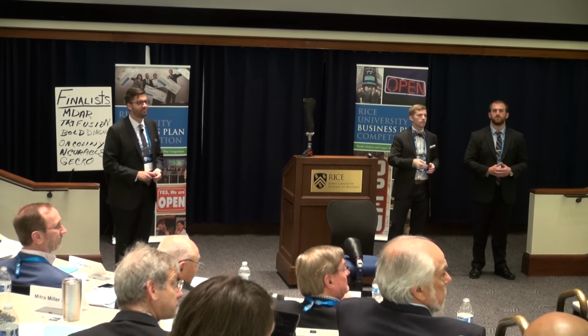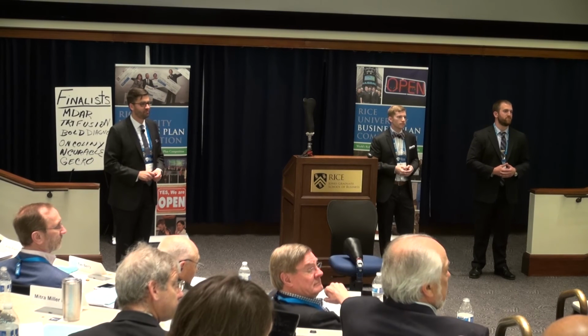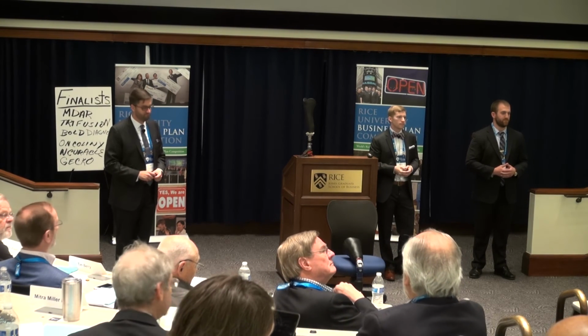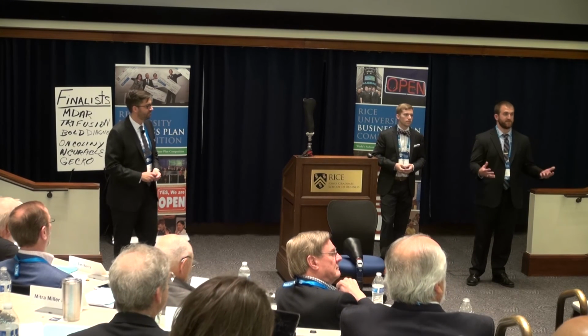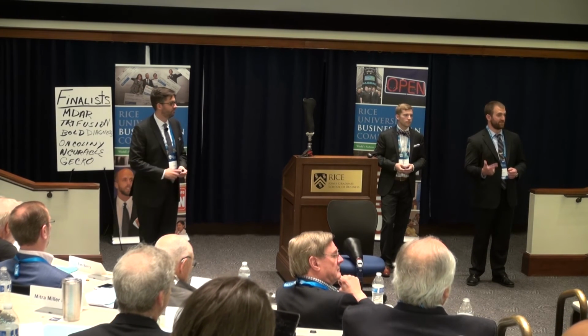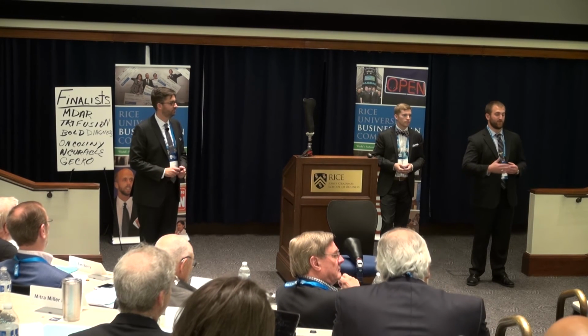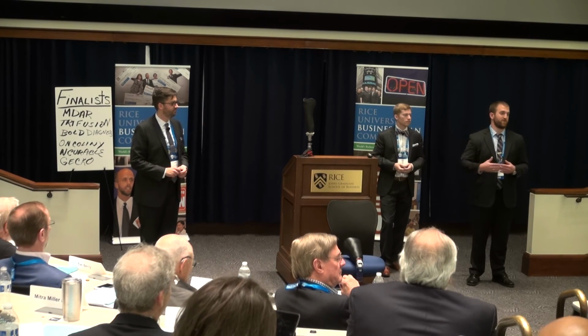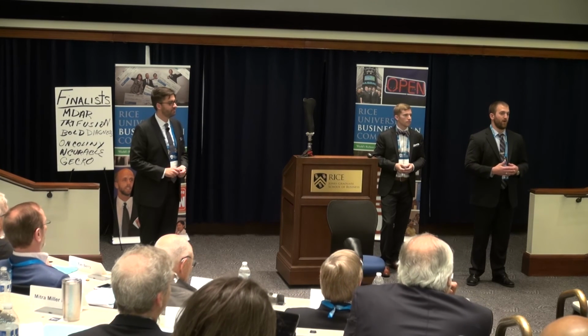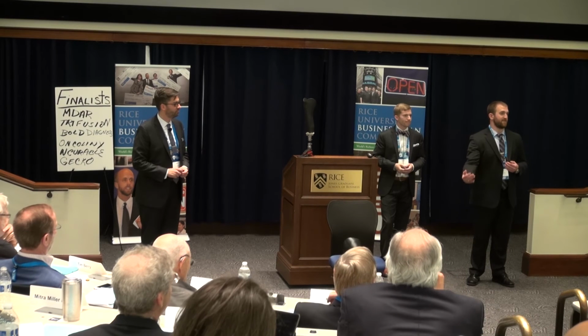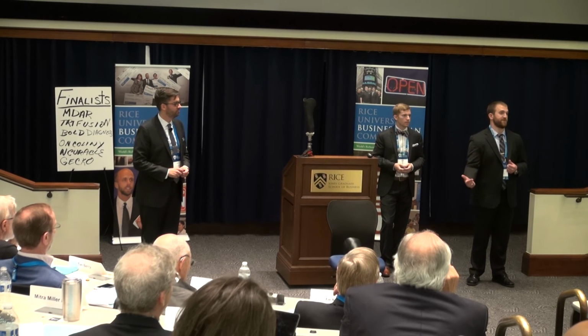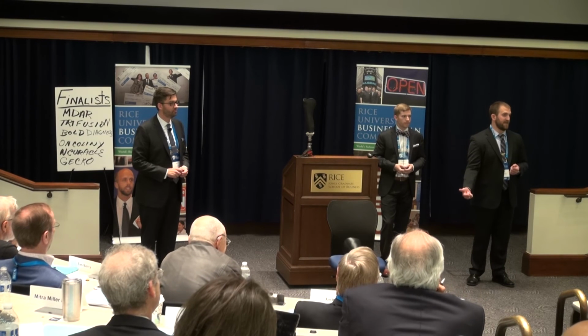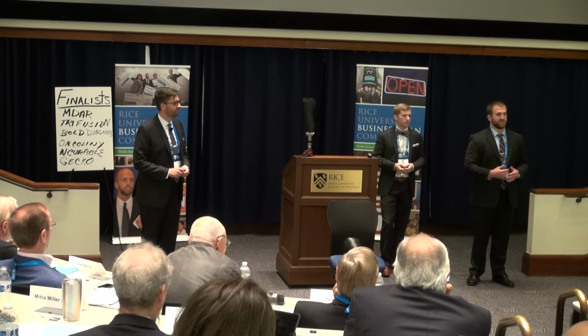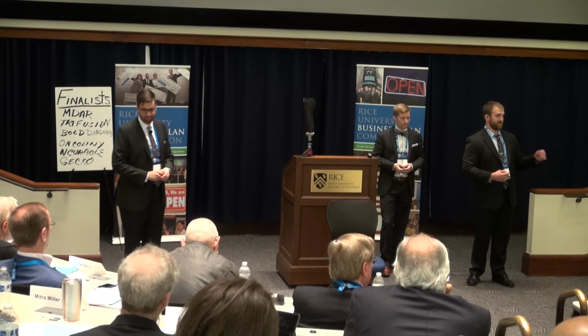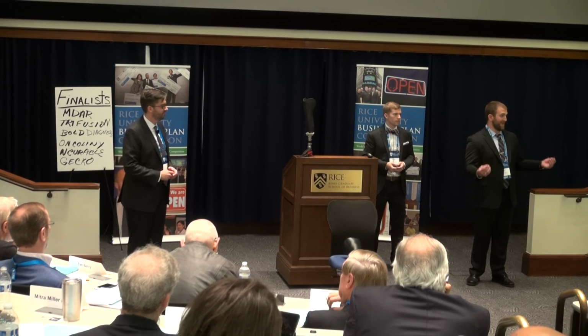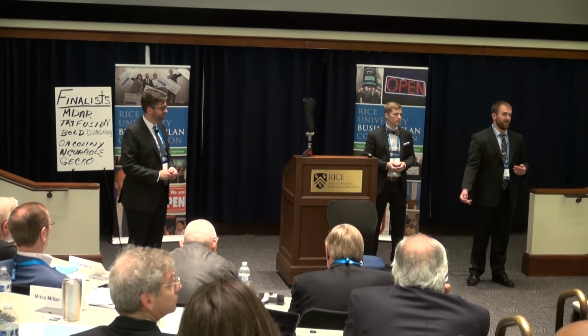I wanted to know about the FDA. What kind of testing does the FDA require for this? And specifically, I believe this is considered a medical device. Yes, sir. So the FDA considers this a Class 1 medical device. There is a predicate device on the market right now that is 510K exempt that we comply with perfectly. So in terms of pre-market notification, we don't have to do it. All we have to do is maintain contact with the FDA, letting them know we're using safe materials, and our products have serial numbers so we can figure out when they fail. Other than that, it's not a lot of market restrictions. And because we're pursuing VAs specifically at first, which are exempt from 99% of FDA oversight, it's awesome.